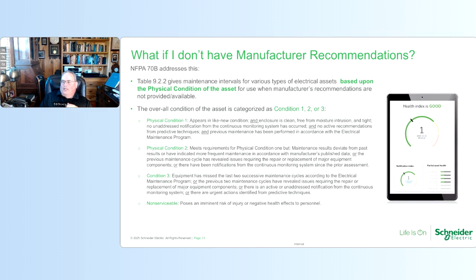However, if all you're relying on is the manufacturer's published O&M literature, you're likely to be locked into a fixed calendar-based maintenance cycle. And we'll talk about that in a minute. So what happens if you don't have manufacturer recommendations? In that case, in NFPA 70B, Table 9.2.2 gives maintenance intervals for different types of electrical assets. These are based upon the physical condition of the asset. They're numbered as condition 1 to condition 3 or non-serviceable.